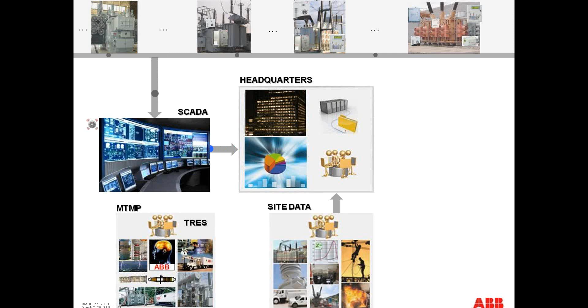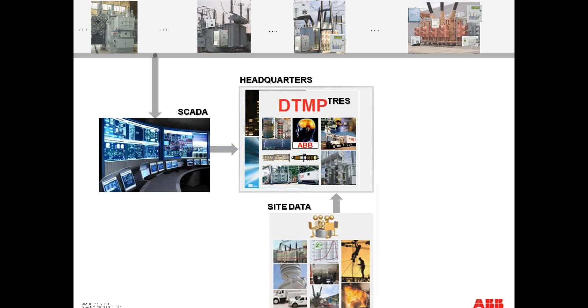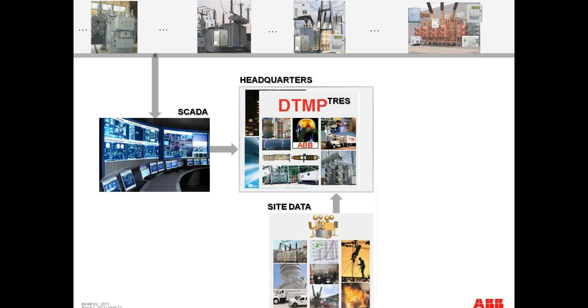Well, we've now figured out how to take those algorithms and embed them on your site, on your transformers, your databases, so that we can wind up continually analyzing your transformers as new information becomes available. And this isn't, in essence, a pitch telling you that you need to put online monitoring there. Any new information that becomes available—if somebody goes out and takes an oil sample, does power factor and capacitance testing, does a thermal scan—all of that information can be constantly updated by these embedded algorithms.